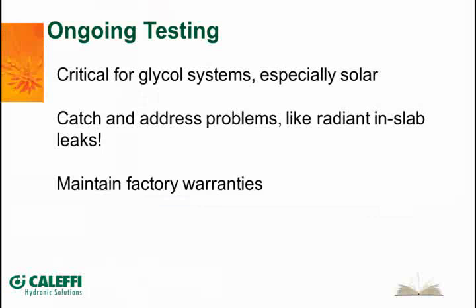Ongoing testing: whatever you put in your system, you want to go back and test it, especially if it's a chemical system or a glycol system. You want to be able to check the percentage of the glycol. You want to make sure that the pH isn't dropping. That's an indication that the fluid's breaking down. You're going to have the same thing if you start putting hydronic conditioners in there. Whatever the product that you put in there, there's going to be a test kit available that you can use to go back in a couple of years and test that. You might have to boost up the inhibitors or something like that.